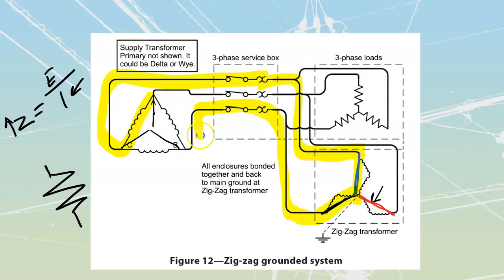The current's going to head back into our transformer. It's going to split some into there and send some into here. It's going to be the same as having unrestricted values of current, but it's going to double up your value of voltage, because it's going from the Y to the delta with direct conduction. So rather than a 600 volt delta system, it would be like you've got a line-to-line short on a 1200 volt one. Very dangerous, can't be done.